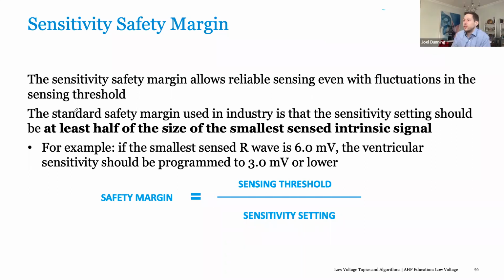Okay. So we then talked about safety margins with capture. There's also a safety margin with sensing as well. And we still use this 2 to 1 idea that you see with capture. So in general, if you have an R wave that's 6 millivolts, you may set your sensing at half of that, so 3 millivolts for your R wave. And that just ensures that you may be able to sense when those values change. Just like capture, sensing can change over time. It can be positional, it could be disease progression, any number of things.